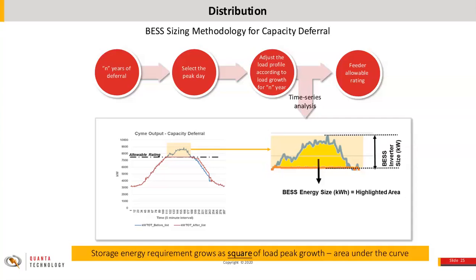If we look at a distribution circuit with a load profile on the left, you can see that it's forecast to go over the rating 2 years out, and we need to do something to add capacity. If we are going to look at storage for deferral, the important question is, am I deferring that capacity 1 year, 3 years, 5 years? How long can I leave the storage there? And if we had a load growth forecast year over year, the peak load would go up linearly with time.